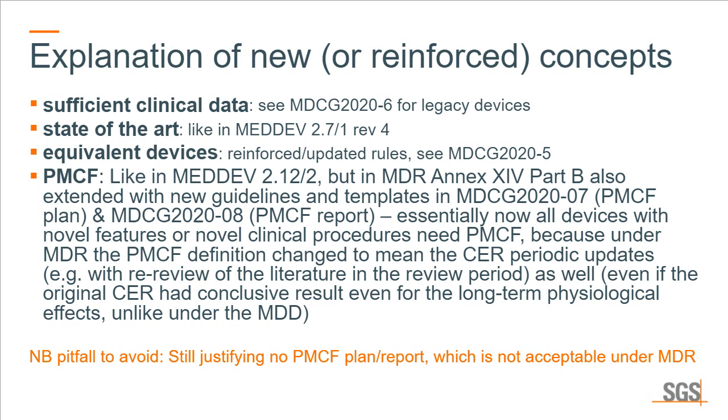2.12/2, but in the MDR Annex 14 Part B also extends this with new guidelines, and there are two templates, the MDCG 2020-7 and -8 for the plan and the report respectively. And so essentially now all devices with novel features or novel clinical procedures need post-market clinical follow-up.